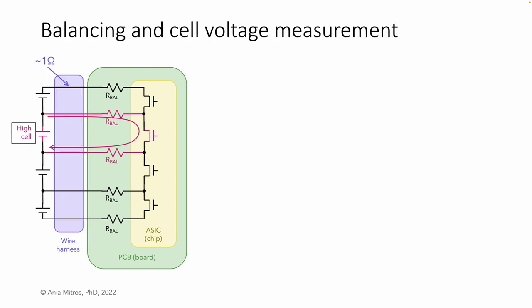Another practical consideration is the impact of balancing on measurement. The wire harness has some resistance, consisting of connectors and the wires themselves. 1 ohm is a plausible connection resistance. BMS ASICs are carefully designed for very low input currents during measurement, to result in negligible voltage measurement error.